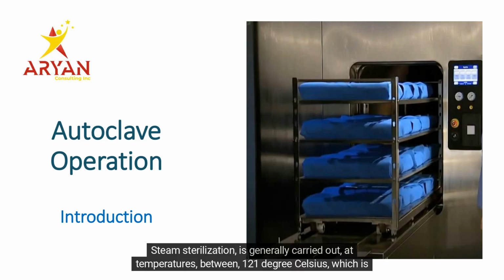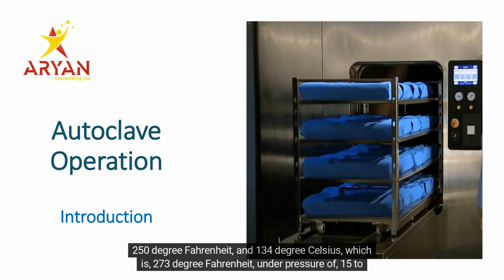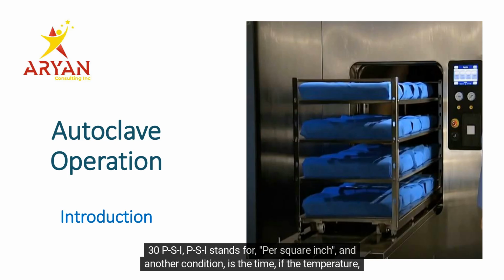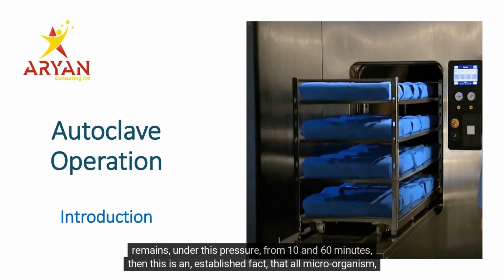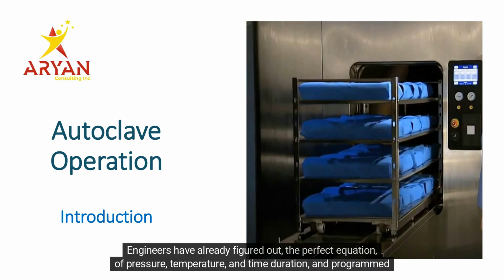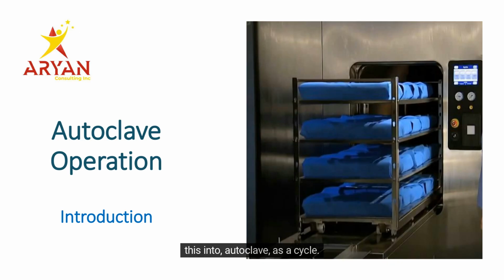Steam sterilization is generally carried out at temperatures between 121 degrees Celsius, which is 250 degrees Fahrenheit, and 134 degrees Celsius, which is 273 degrees Fahrenheit, under pressure of 15 to 30 psi. PSI stands for pounds per square inch, and another condition is the time. If the temperature remains under this pressure for 10 to 60 minutes, then this is an established fact that all microorganisms have died. Engineers have already figured out the perfect equation of pressure, temperature, and time duration and program this into the autoclave as a cycle.